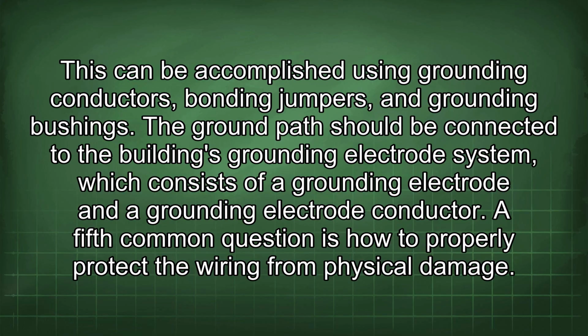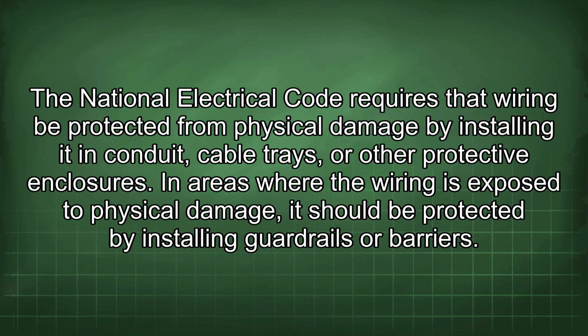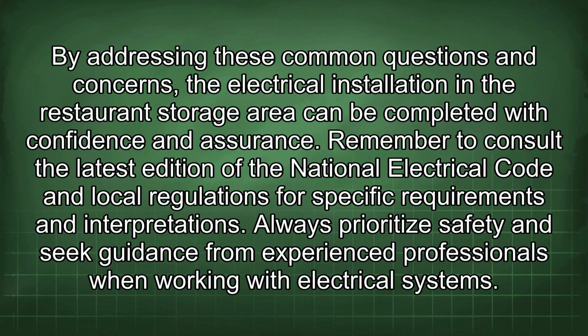The ground path should be connected to the building's grounding electrode system, which consists of a grounding electrode and a grounding electrode conductor. A fifth common question is how to properly protect the wiring from physical damage. The National Electrical Code requires that wiring be protected from physical damage by installing it in conduit, cable trays, or other protective enclosures. In areas where the wiring is exposed to physical damage, it should be protected by installing guardrails or barriers. By addressing these common questions and concerns, the electrical installation in the restaurant storage area can be completed with confidence and assurance. Remember to consult the latest edition of the National Electrical Code and local regulations for specific requirements and interpretations. Always prioritize safety and seek guidance from experienced professionals when working with electrical systems.